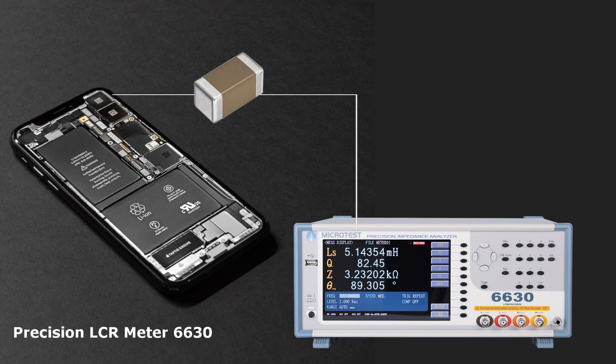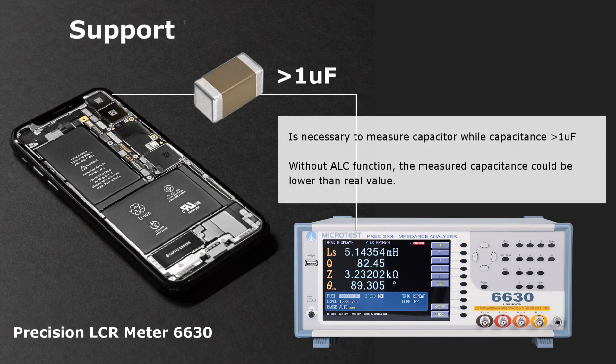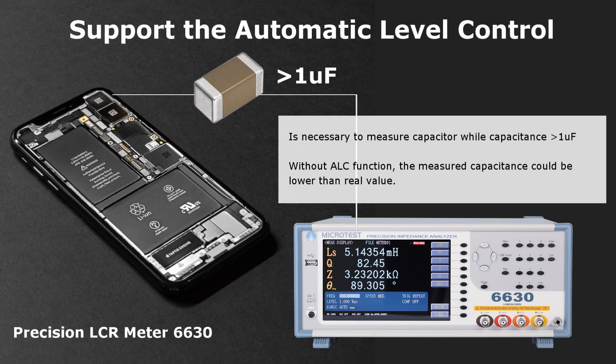For MLCC, the Automatic Level Control function is necessary to measure capacitors with capacitance greater than 1 uF. Without this function, the measured capacitance could be lower than the real value.